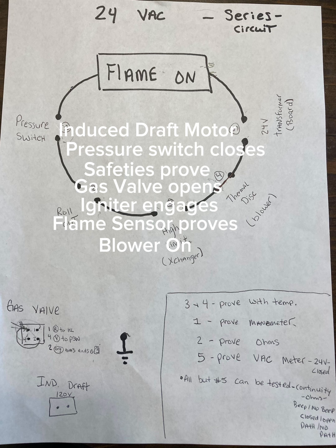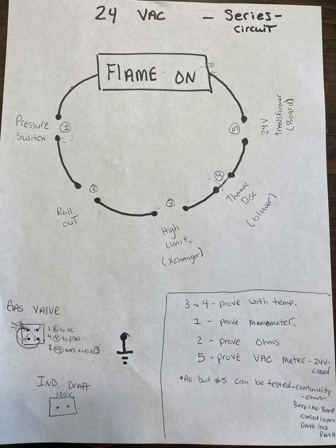If I'm getting all the way to my gas valve is open, I don't need to be looking at the pressure switch. Is it closing or not working? Is my thermostat not sending the right call? Is one of my safeties open? Well, they're all closed because the gas valve itself opened. You heard it. You saw that click. And you noticed to look beyond the gas valve. That's where you start. So what's that igniter looking like? How does it spark? And what's going on there?